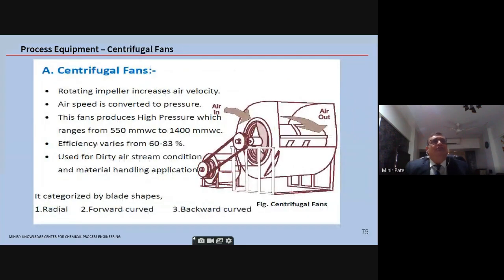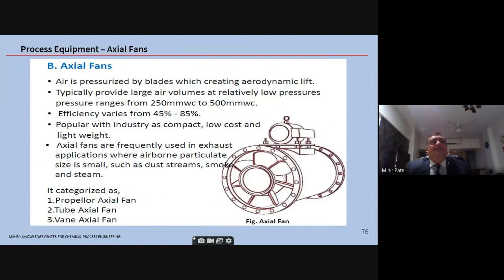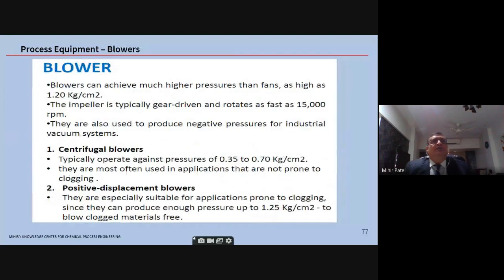So centrifugal fans, as you can see, are of 3 types: radial, forward curved, backward curved, and certain other characteristics are shown here. Axial fans are, as I mentioned, very low head. You can have different types here: propeller axial fan, tube axial fan, vane axial fan. Blower is there, which is used in pneumatic conveying services, as I mentioned. So here you can see centrifugal blowers are there, and positive displacement blowers. So this can be used to blow clogged materials free. So this is definitely the roots blower category used for pneumatic conveying applications.